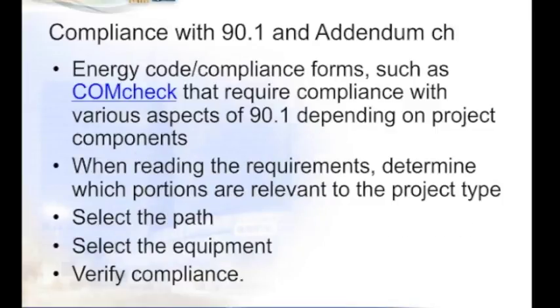Now to have a short discussion about compliance with 90.1 and Addendum CH. Compliance with these new requirements in 90.1 related to chiller efficiency will still be accomplished in the ways we use for current projects. ComCheck is a fairly standard proof of compliance form, which is used and accepted by many plan review authorities. In my own case, we've personally used output reports from our energy modeling software as well to prove compliance with these requirements. It is important to consider which portions of the updated standard are relevant to your project.